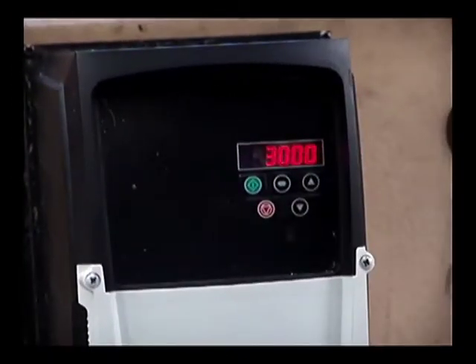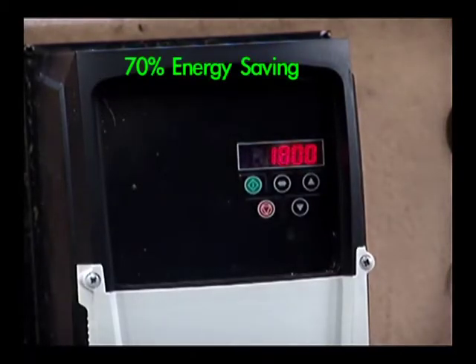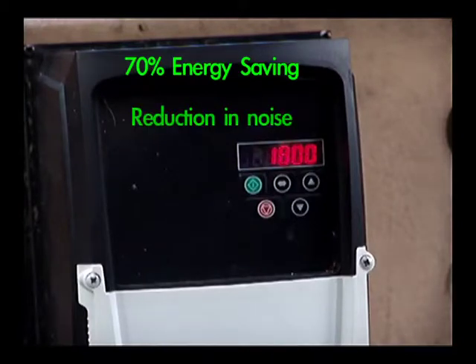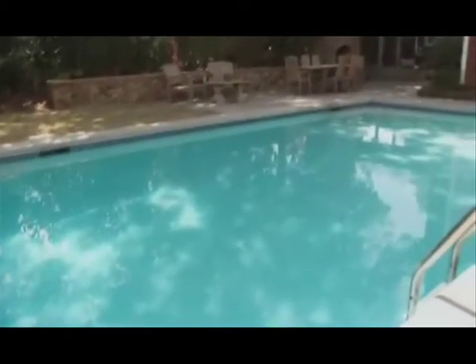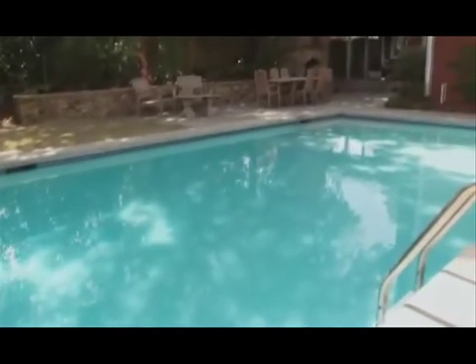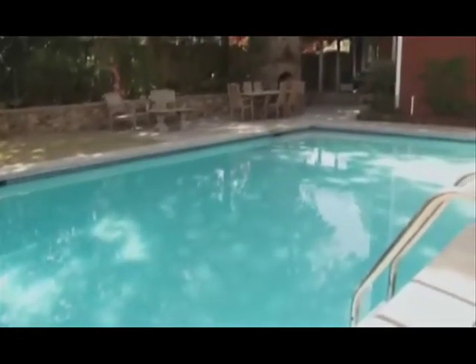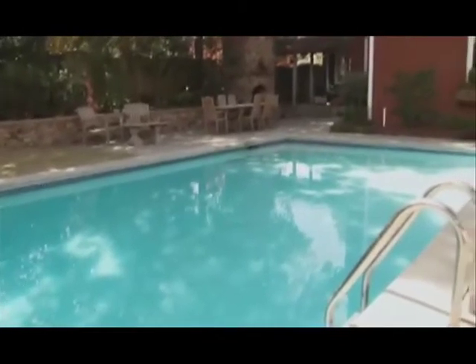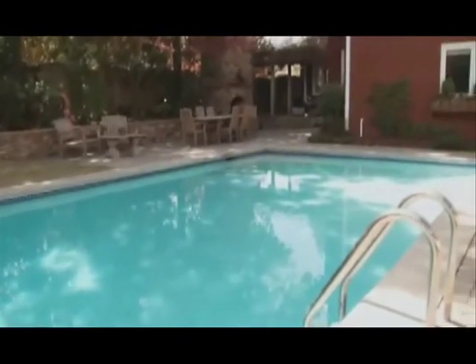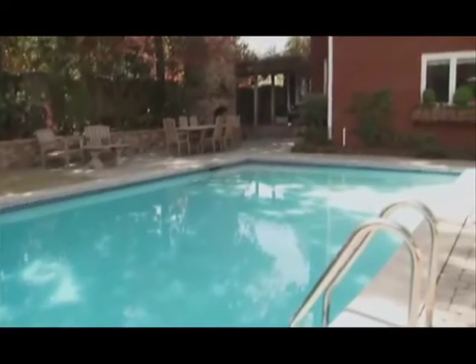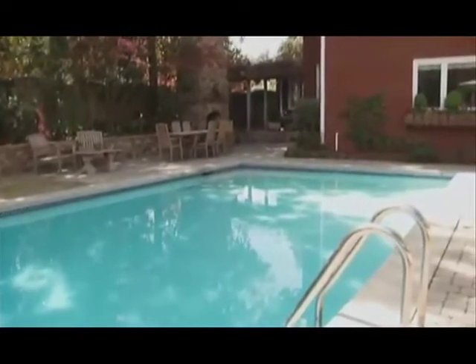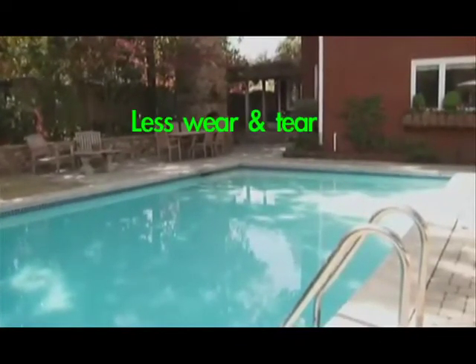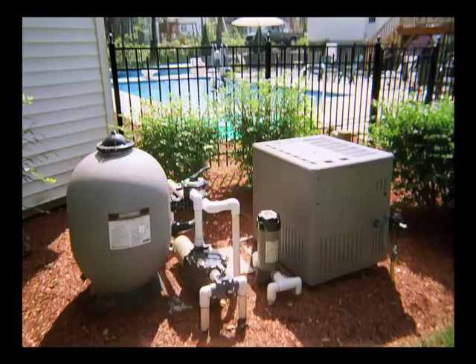60 seconds have passed and you can now see that the pump is running at 1800 RPM and at 30 Hz, achieving a 70% energy saving and with a significant reduction in noise. Your pump is now consuming the correct amount of power to run your pump efficiently without any detriment to the flow rate of the water. As the controller drops down to 1800 RPM, the noise is reduced. The pump motor is spinning slower and causing less wear and tear, thereby extending the life of the motor.